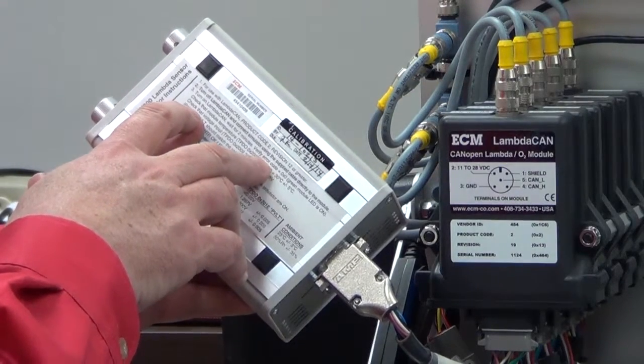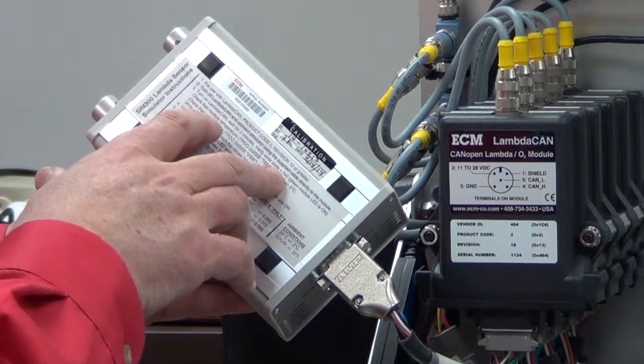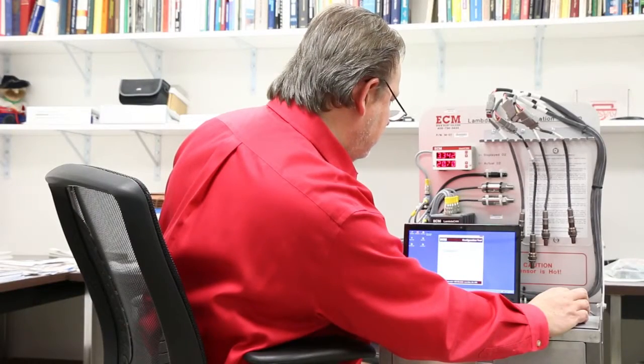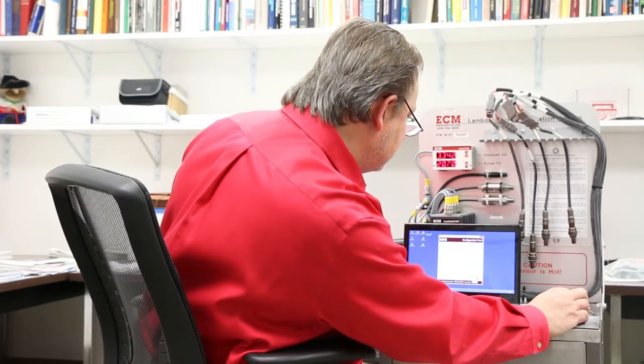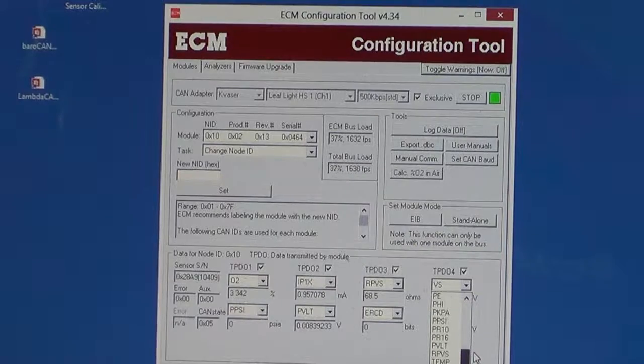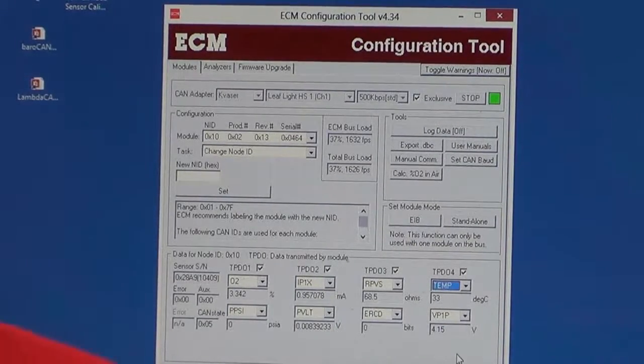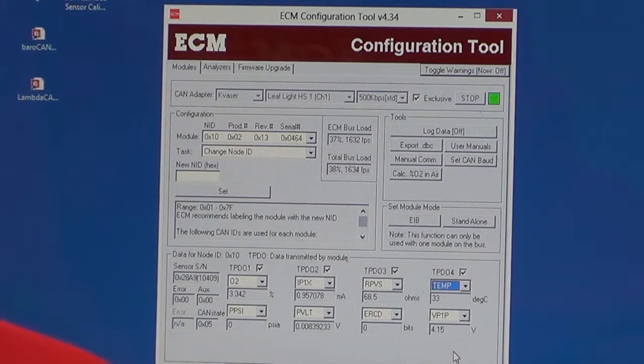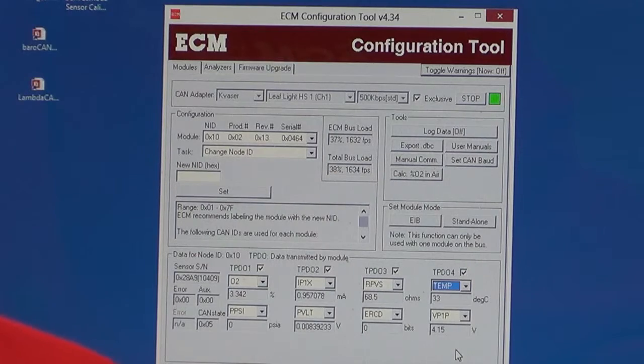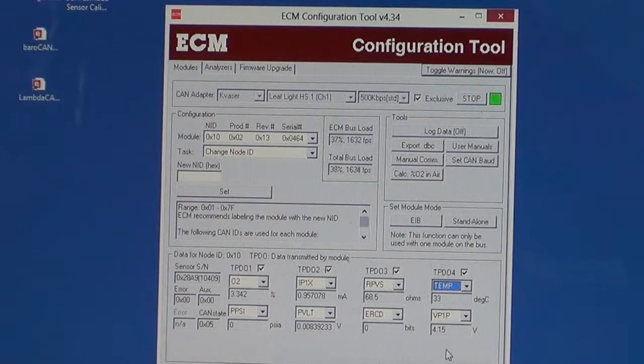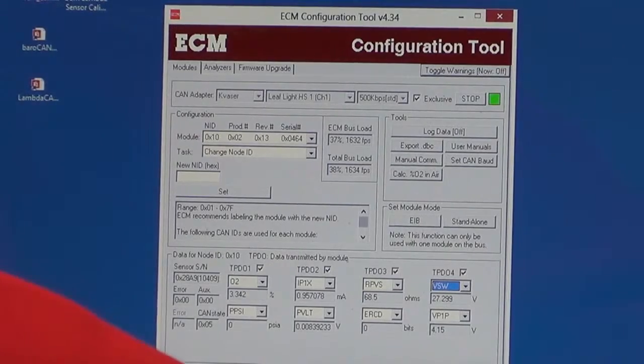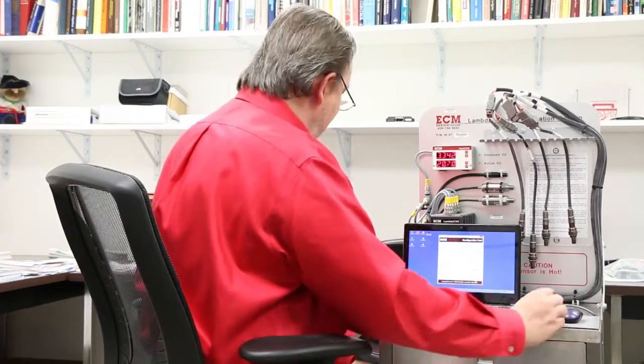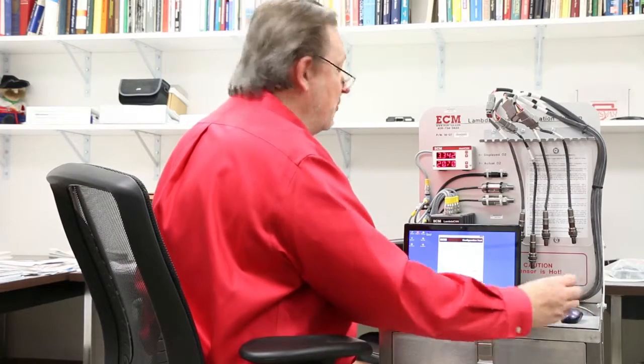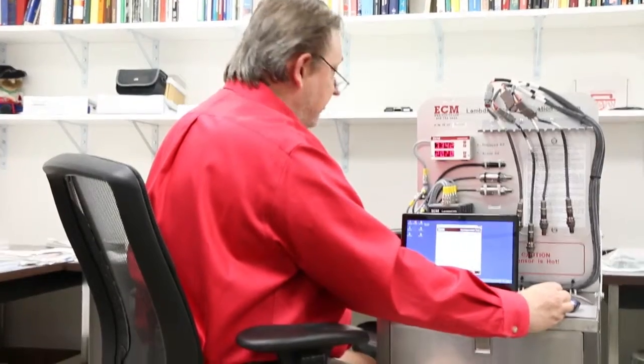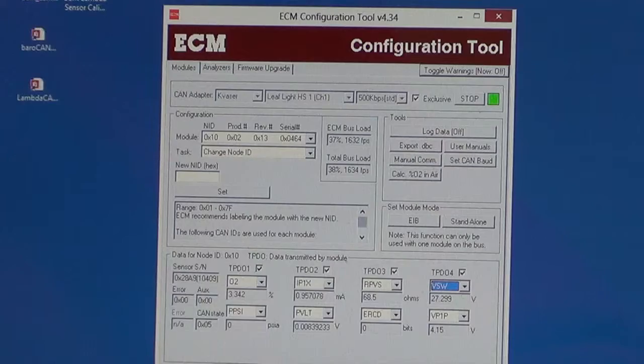Now check that module temperature is 30 degrees Celsius. So you pull down this menu, and you go to find temperature. There it is right there, temp. There's 33, plus or minus 5 degrees. Well, we're within specs. All right, the voltage input should be between 11 and 28 V switch, so pull down here. VSW, there it is, 28. You're not going to have these problems with this setup because of the power supply we use, and you're going to be doing it in a room, but in case you're using this calibrator on a vehicle out in the snow.